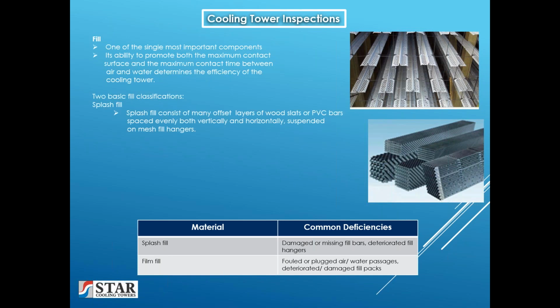There are two basic fill configurations or classifications. Splash fill. Splash fill consists of many offset layers of wood slats or PVC bars spaced evenly both vertically and horizontally, suspended on mesh fill hangers. These mesh hangers that the fill is suspended on can be PVC coated galvanized wire, stainless steel wire, or glass reinforced polyester grid hangers, and these need to be maintained in good condition to keep the fill installed firmly and evenly in the tower.